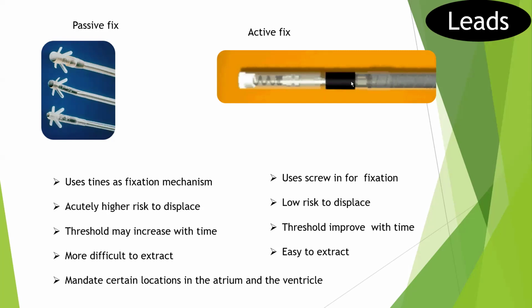We know that if you want to extract a lead implanted more than 1 year, most of the time it will be well adhered, well attached to the myocardium, and you need to use a special type of laser extractor to be able to remove that lead. But with the active fixed lead, it is less adhered to the myocardium through a fibrous mechanism, because of, one, the steroid coating, and two, the main mechanism of connection is through screwing the lead into the myocardium. And it is not very long. The screw is most of the time 1.8, maximum 2 millimeters in length. So it is not a large screw that may result in perforation and tamponade. So this is the preferred type of lead now, and almost all the leads available now are active fixed. You will hardly find a passive lead for a pacemaker.